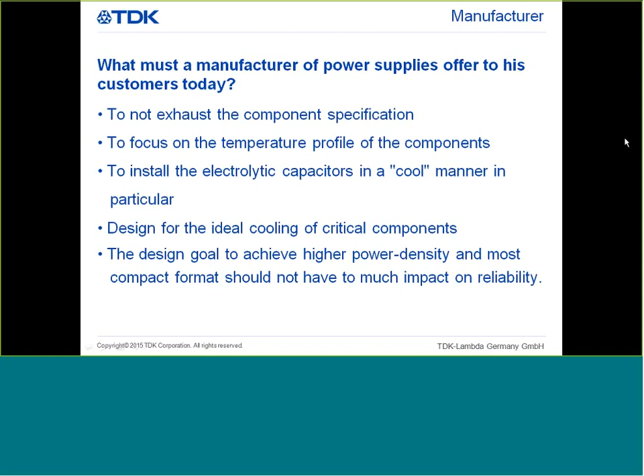TDK-Lambda has temperature profile information in its reliability data. Here, a component derating list is added. The table describes a margin between nominal operation values and the specification of each component. This overview presents a percentage of load in each component in relation to its specification. The main components temperature rise list then follows. It's an overview of the heating of the components under nominal load. The curves of the electrolytic capacitor lifetimes in the power supply unit finally follow.